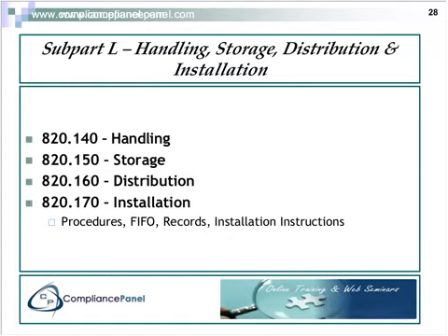There's also a requirement that you keep records of any installations you perform. So if you're installing a big system such as an MRI system, you need to keep the records of those installations, and you also have to write instructions for how the installation should be done. In some cases, for very large equipment, such as an MRI system, you would get a site plan from the hospital, or you would provide them with a site plan as to how much area they need to install a device such as that. So that's where installation instructions would be important.